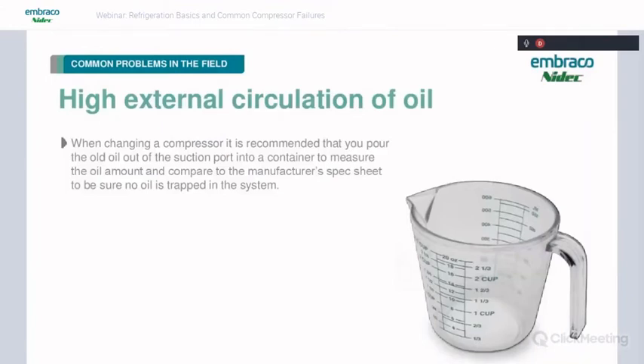So one of the problems that is not talked about too much, but you could have some oil that has left the crankcase and has gotten trapped out in the system. For whatever reason, the compressor's going bad. You've got dirty coils, and you could get some oil trapped in the evaporator or the condenser. And what's going to happen is when you go put the new compressor in, you get normal pressures going again. All of a sudden, a big old slug of oil is going to come back to the compressor and hit the valves, break the valves, or it's going to overfill the crankcase and cause problems.